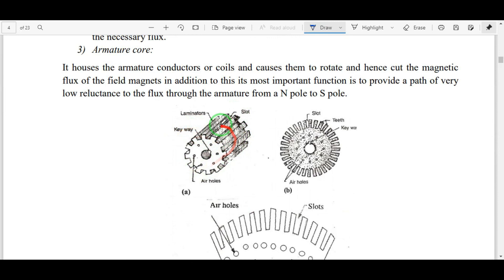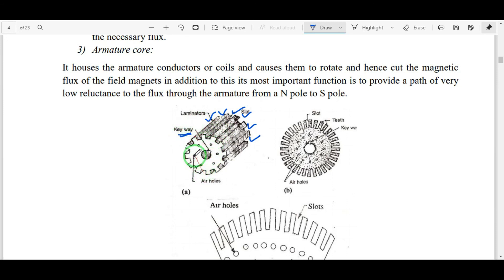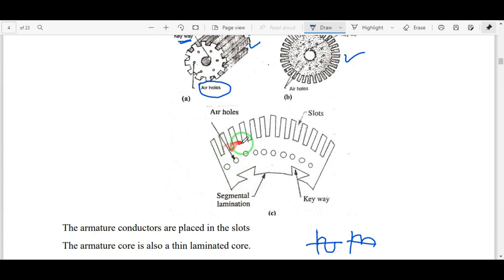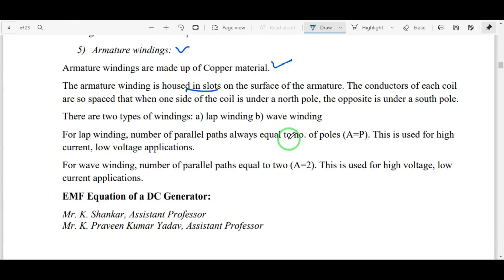The armature core consists of slots, and a winding is wound in each slot. The armature core is not a solid part — it is a laminated structure. Multiple laminated sheets are combined to form the armature core. Each laminated sheet has a keyway to fix it to the shaft and air holes to circulate air for cooling. Armature windings are placed in these armature slots.